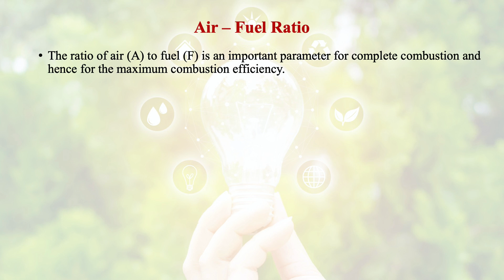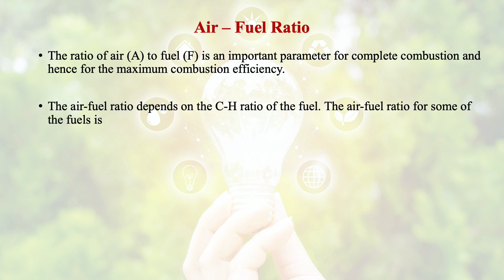The combustion efficiency is optimized when the proper air and fuel are supplied and mixed, when the combustion losses are minimized, and third, when incomplete combustion is avoided. Then comes the air-fuel ratio. The ratio of air to fuel is an important parameter for complete combustion and hence for the maximum combustion efficiency. The air-fuel ratio depends on the carbon-hydrogen ratio of the fuel.